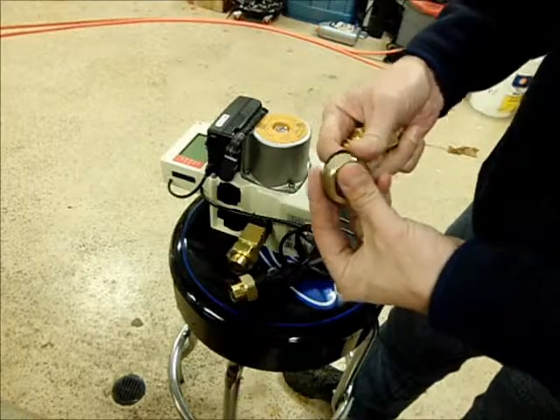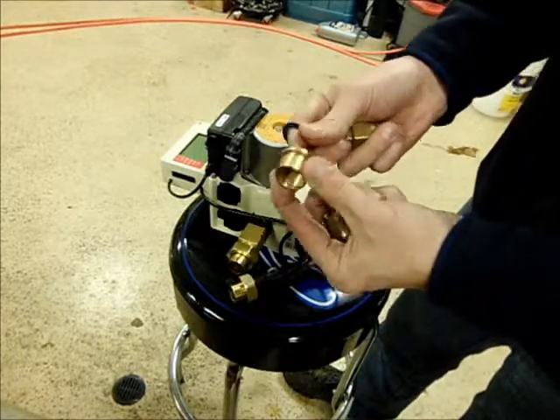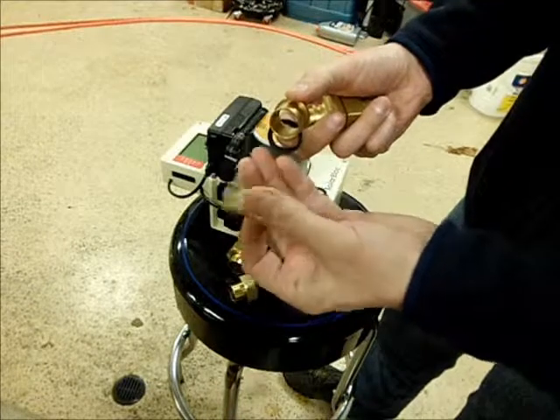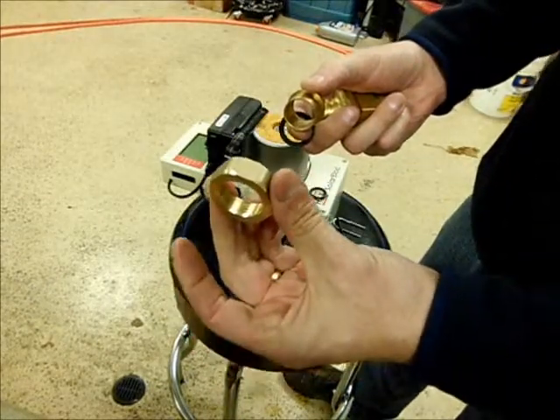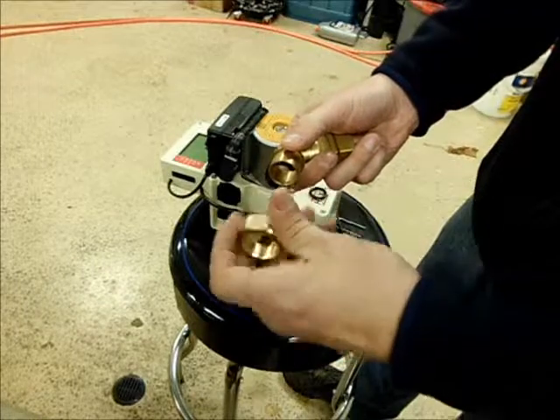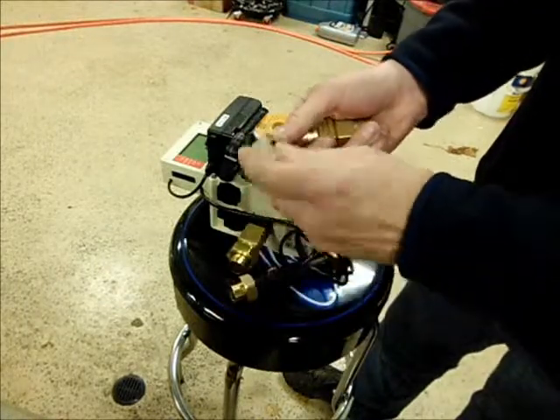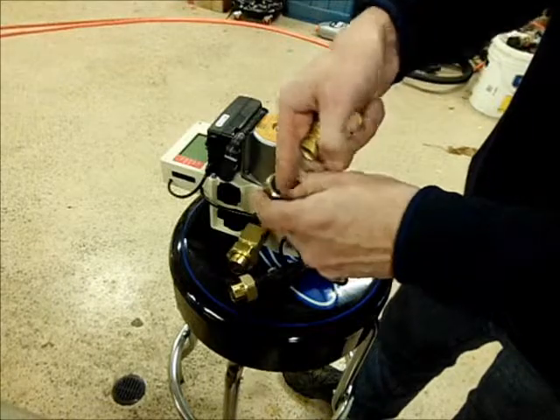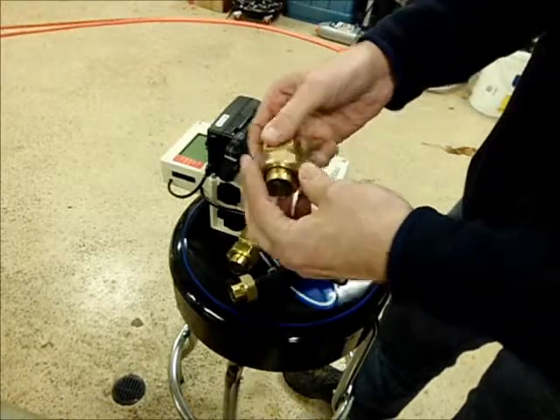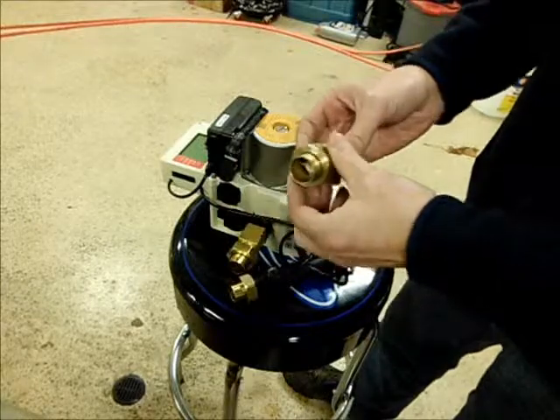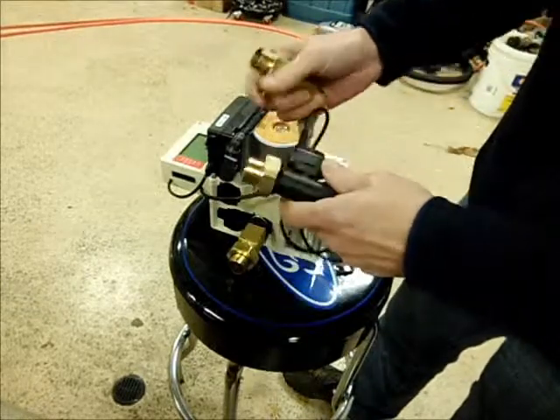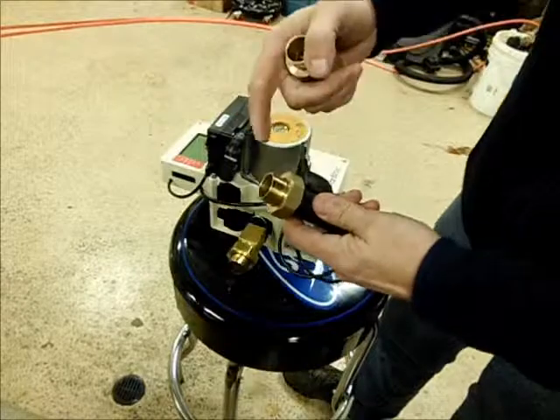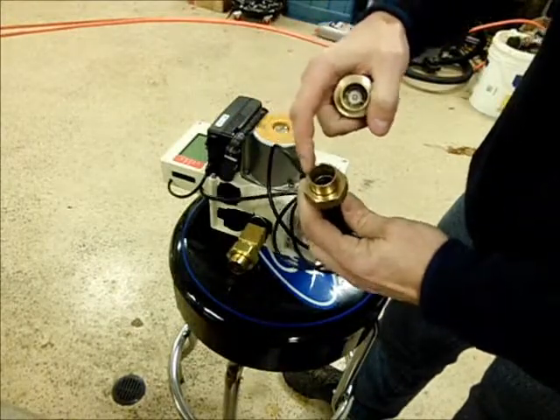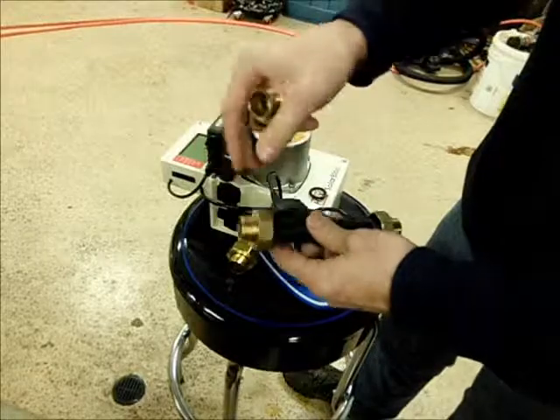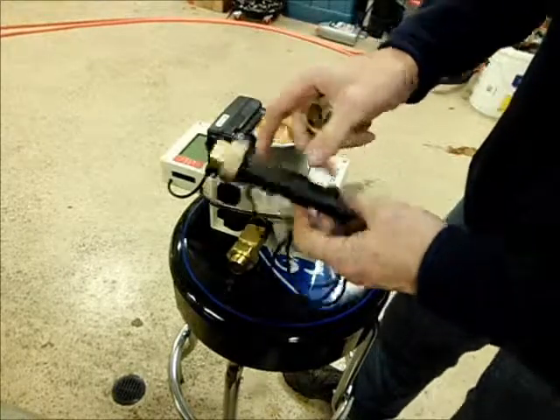Now these pieces here will get sweat soldered to your 3/4 pipe. Make sure you slide the nut over the pipe first, make your solder connection, slide the nut forward, put the rubber in there, and fit it on the end of the fitting. Okay? Same thing goes for your flow sensor. You want to pull these off, make your sweat fittings, solder onto here, 3/4 inch pipe. When it's all cool, then you bolt it up, because this is a resin type plastic, so you don't want to be doing any soldering on this plastic.